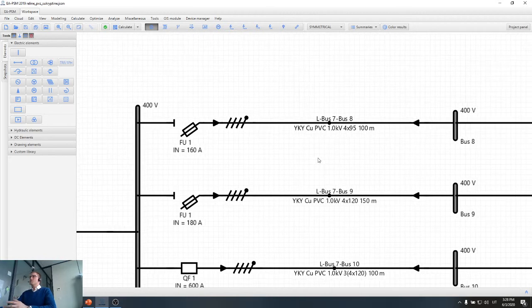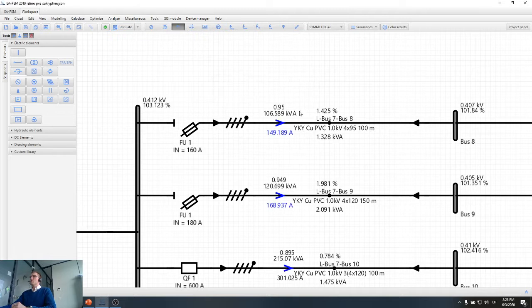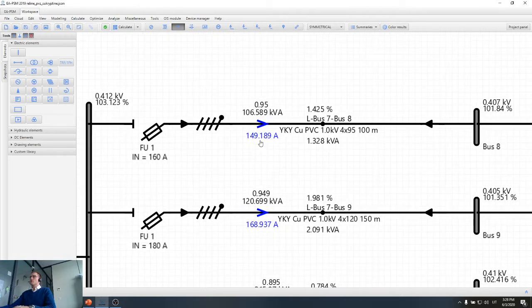There are several possible ways. One of them is just to read the manufacturer datasheet of the inverter. In the inverter datasheet you can most often find the recommended fuse rating. Another way is to use our software to calculate the normal current for the inverter. We can see that the normal current is 149 amps. This means that we need to select a fuse with a nominal current bigger than the normal current, so that our fuse will not disconnect during normal operation.